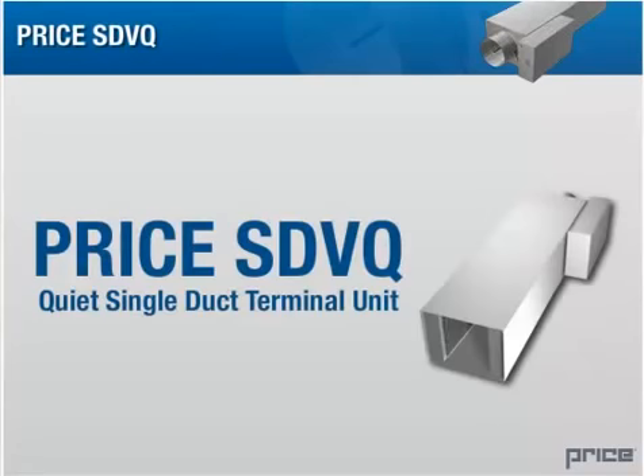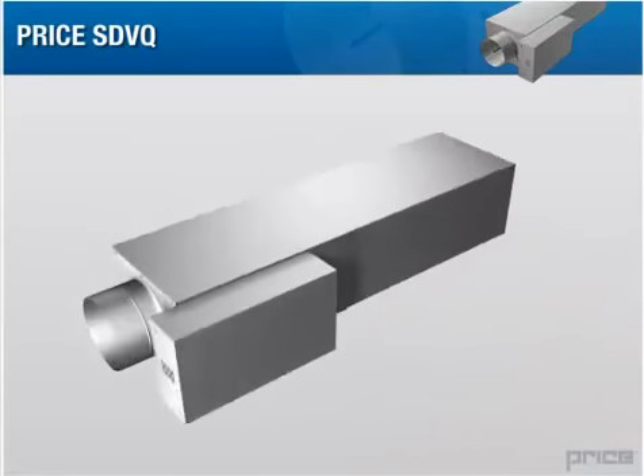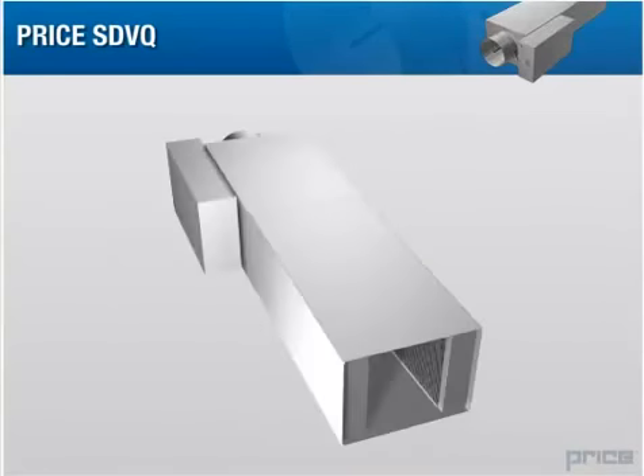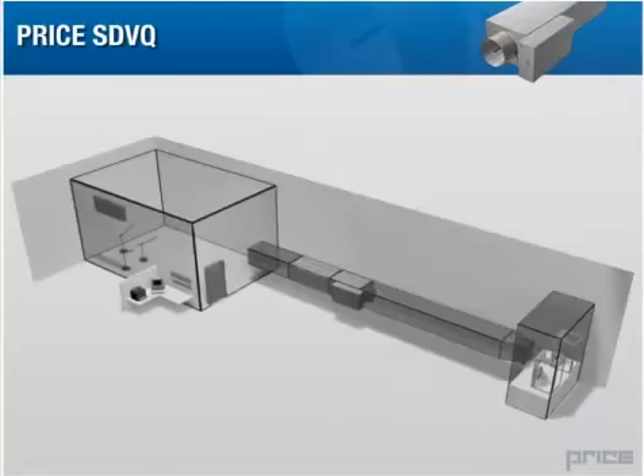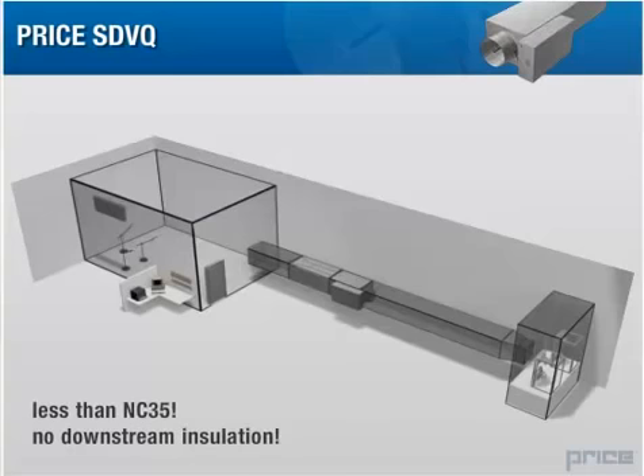Price SDVQ, Quiet Single Duct Terminal Unit. Price's Single Duct Q Series VAV terminals are the HVAC industry's first strategically designed, fully tested, and ARI certified integrated VAV silencer terminal units. This terminal integrates both VAV and silencer technology into one complete package. Extensive lab testing was used to determine the best combination of terminal and silencer configuration, resulting in an assembly which achieves room noise levels of less than NC35 without the addition of downstream acoustic insulation.